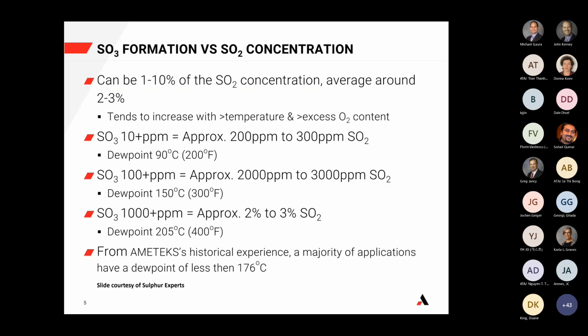So what happens is sulfur trioxide will combine with water on surfaces when it hits the dew point and form sulfuric acid, H2SO4. This is a severe corrosion product of the combustion process, and it will cause all sorts of problems with your wetted sample lines and the analyzer itself. As we increase in concentration of SO2, you can see that the dew point rapidly goes up. From 10 ppm to 100 ppm SO3, we go from a 90 degree C dew point to a 150 degree C dew point. At 1,000 ppm SO3, which is basically 2 to 3% SO2, we're sitting at a dew point of about 205 degrees Celsius.